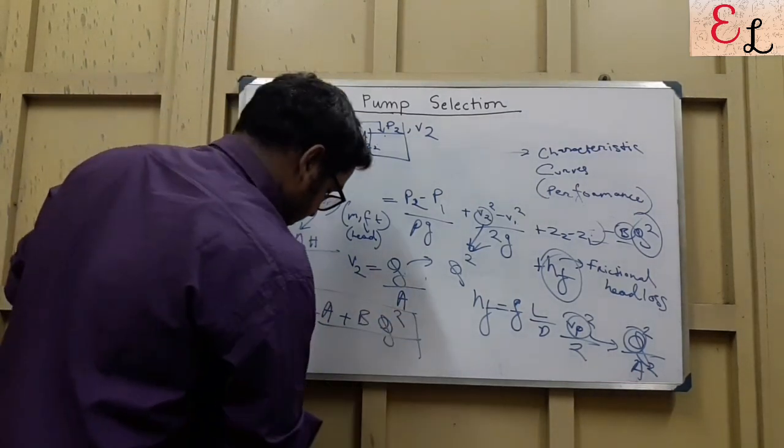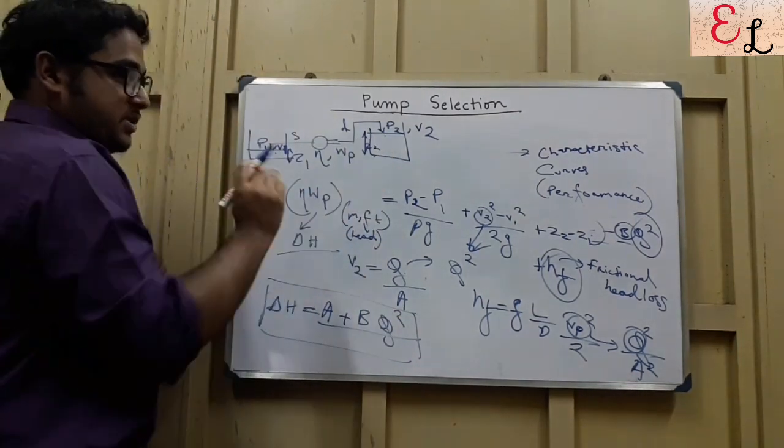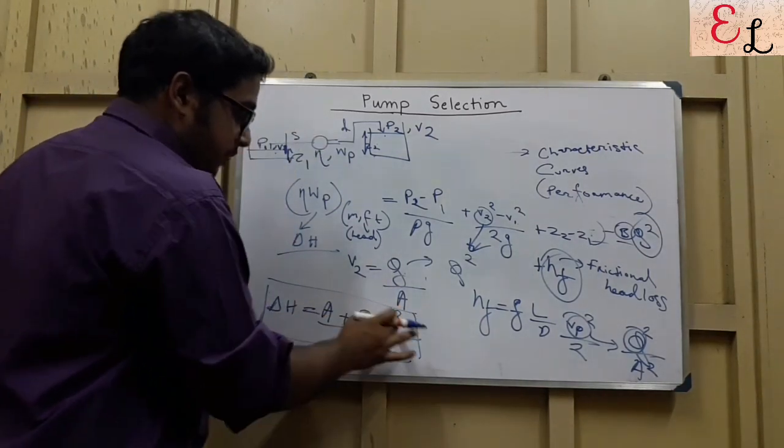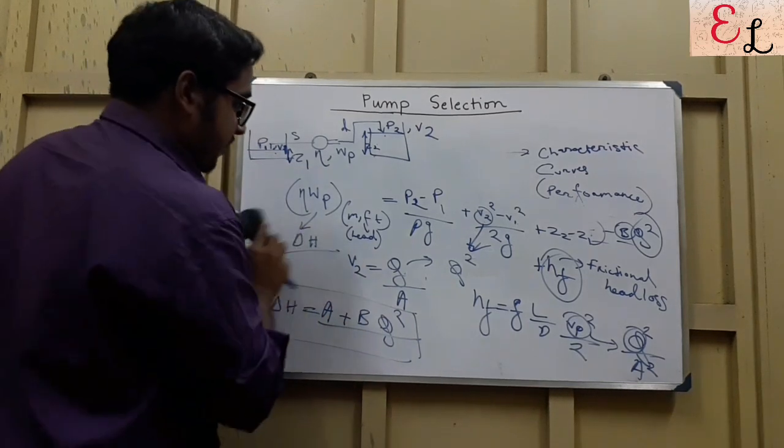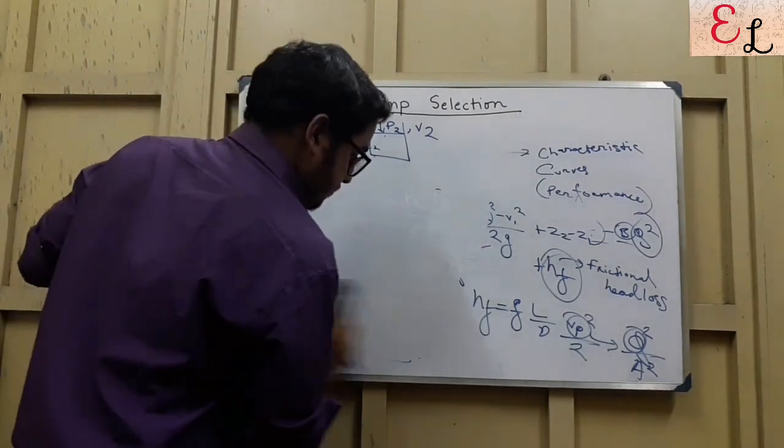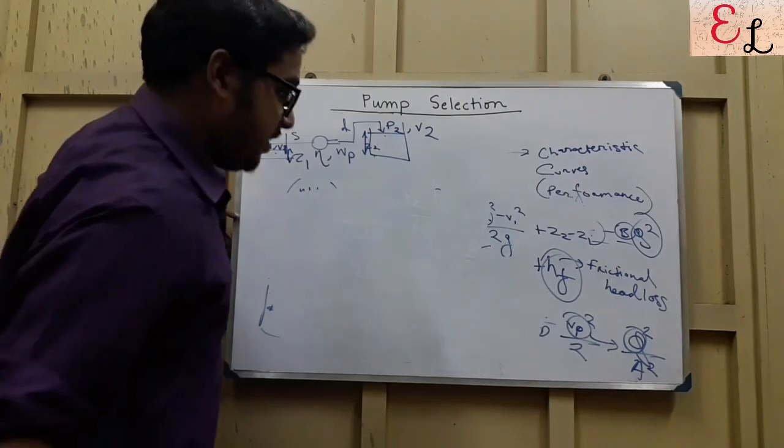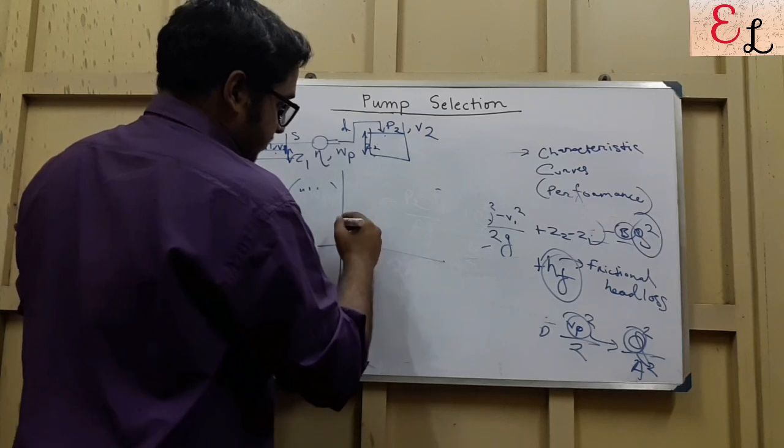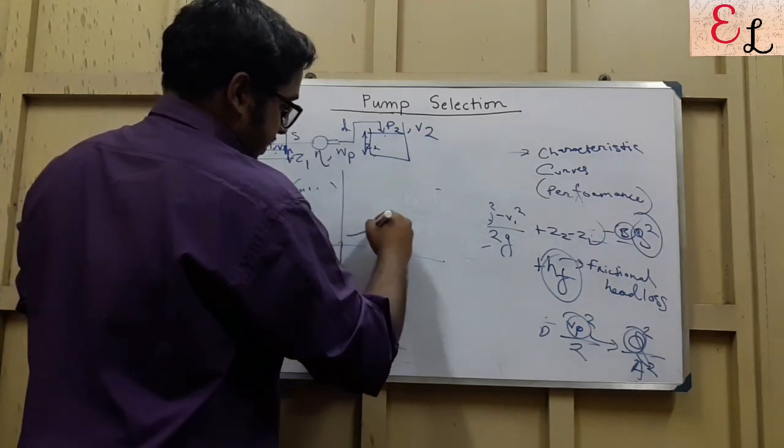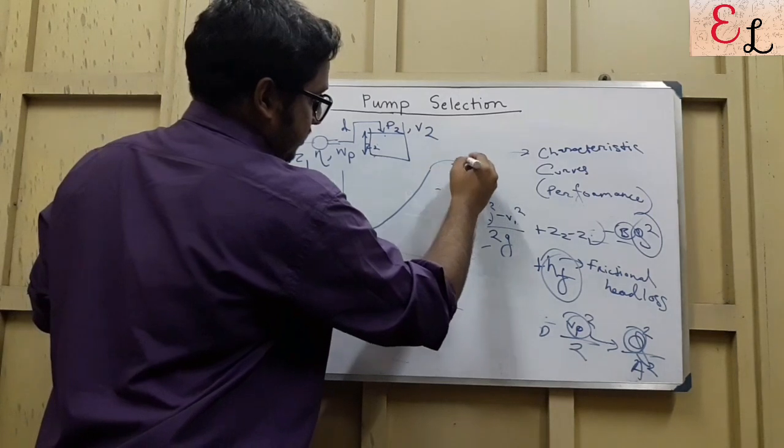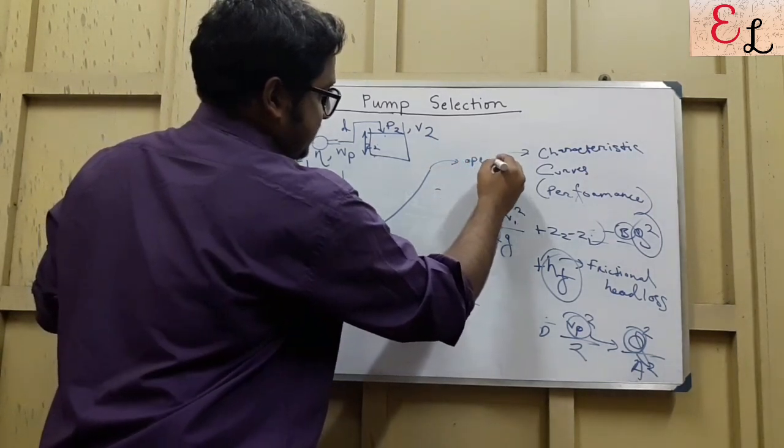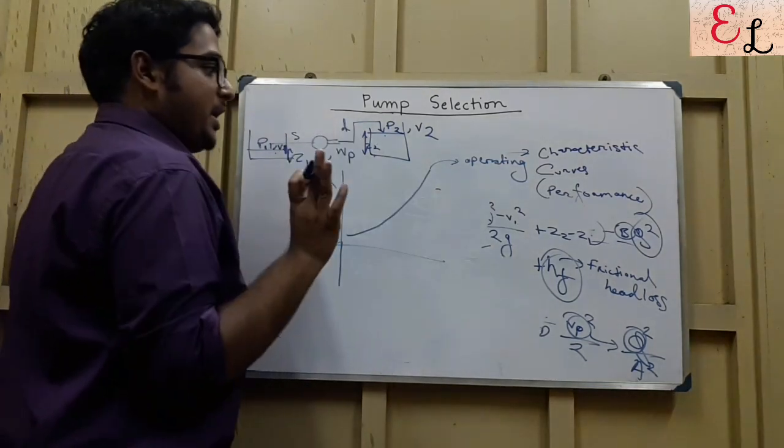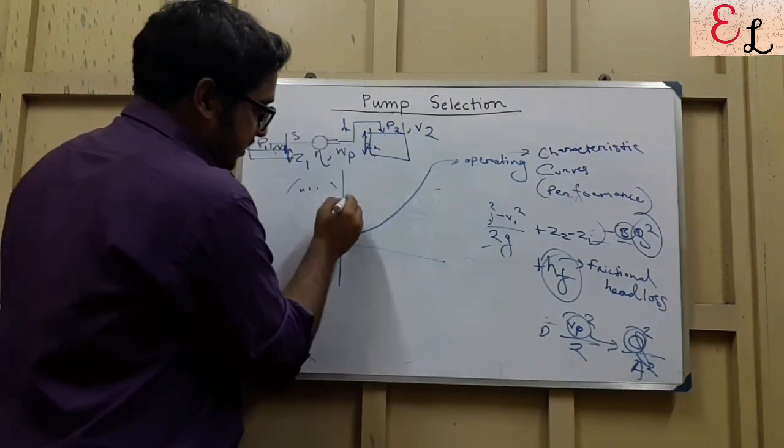So operating conditions from the normal energy balance equation, you see the operating conditions give us a shape where this is directly proportional to Q square. Now if we refer to the curve, we will find something like this, the operating line. This is the operating line. And it's the same for any pump, irrespective of the pump number, the operating line does not change. What changes is the characteristic curve.